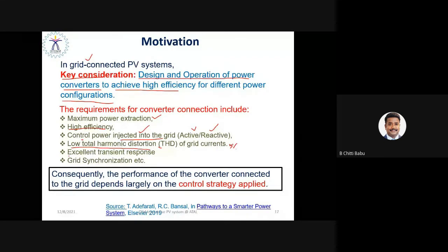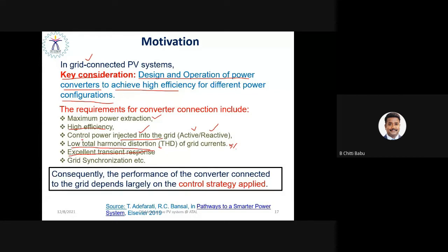And further, it should have an excellent transient response. The transient response is very essential, as it ensures grid stability. When the grid is under abnormal condition, it should still have the stability to sustain. Of course, it needs fault ride-through capability, so that the energy can be restored without any interruption. And further, grid synchronization is very essential to match the inverter output frequency with the grid frequency. Both must be synchronized at the fundamental frequency, 50 Hz. Then we can have the possibility of successful integration. This is the key motivation for grid integration of solar PV system.